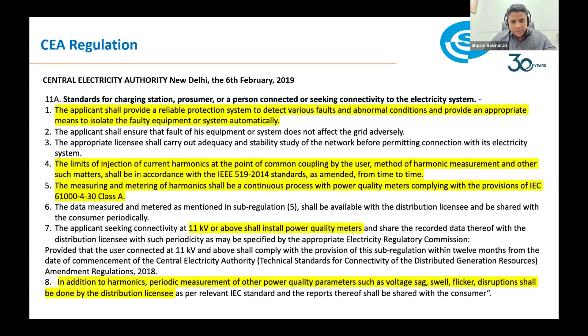Now, some of the common power quality issues. I'll bring a couple of important ones, though there are a lot of inclusions in power quality. Let me pick out some handful of definitions which are important for the larger context. Our major concerns are sag, swell, and unbalance. So coming back to the definition, IEC will always define it with a tolerance. So the sag defines the tolerance with a certain percentage. There can be a temporary reduction of a voltage magnitude at a point in an electrical system below a threshold. So how do they define what the threshold level is? 10% to 90% of the nominal value, lasting from 0.5 cycle to 1 minute. If it goes beyond this, according to the reference, it is considered a sag. We call it an event.